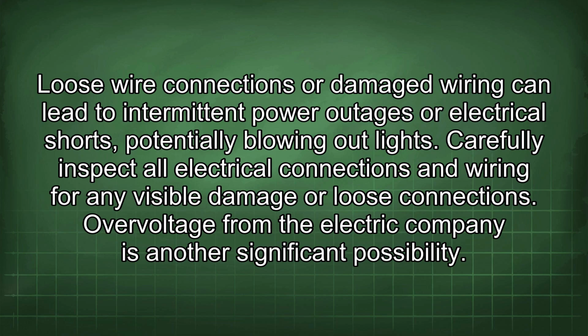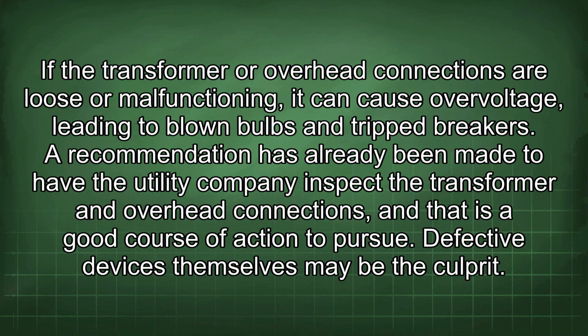Overvoltage from the electric company is another significant possibility. If the transformer or overhead connections are loose or malfunctioning, it can cause overvoltage, leading to blown bulbs and tripped breakers. A recommendation has already been made to have the utility company inspect the transformer and overhead connections, and that is a good course of action to pursue.